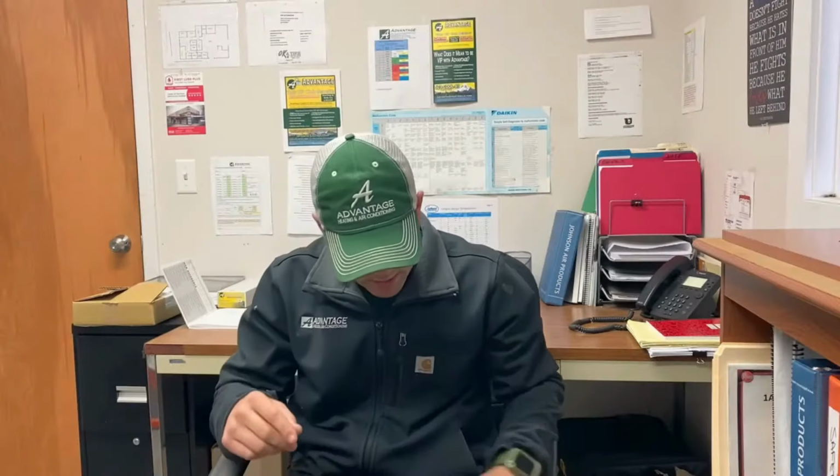The last thing that I'm going to talk about is the positioning of a dryer vent. With this call, I went out there. The system was locking out on high head. The dryer vent was blowing, and they haven't had a cleaning on the dryer vent. And the dryer vent was right next to the heat pump. And what happened, the dryer vent lint actually got sucked up inside the coil and it plugged it.